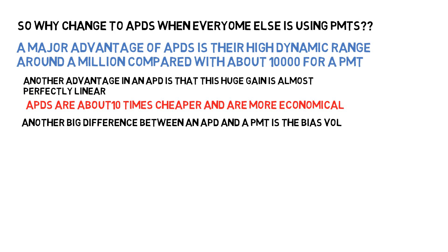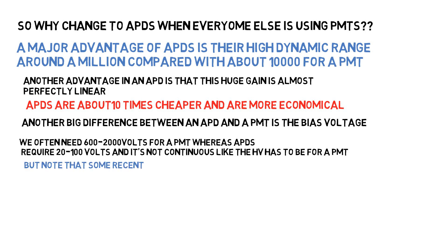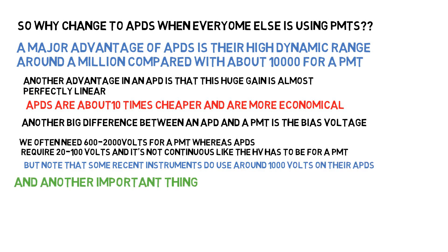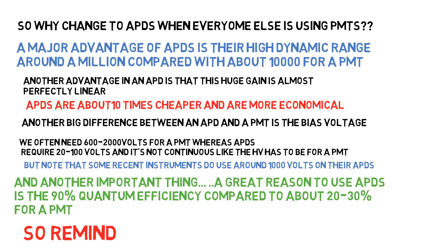Another big difference between an APD and a PMT is the bias voltage. We often need 600 to 2,000 volts for a PMT, whereas many APDs require only 20 to 100 volts, and it's not continuous like the high voltage has to be for a PMT. Although some APDs in some instruments use around 1,000 volts. Another great reason to use APDs is their almost 90% quantum efficiency, compared to maybe 20 or 30% for a PMT.